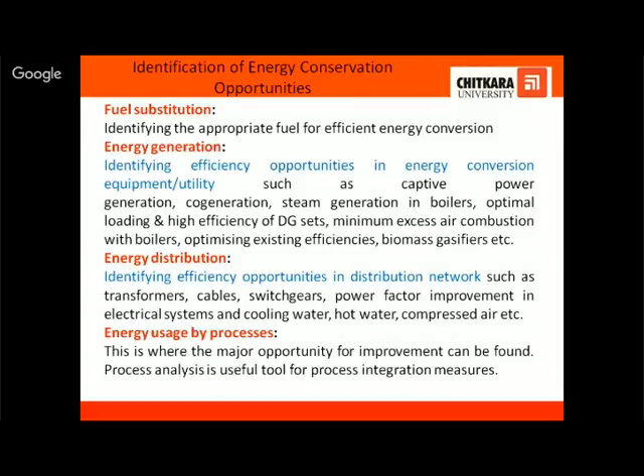Then we talk about the energy distribution systems. We can work out where energy efficient opportunities exist, like in transformers and cables. If there are loose joints of the cables, or the terminations are not done properly, then a lot of energy gets wasted. And sometimes the cables are overloaded. If they are not sized properly, then again power loss is occurring. Then what about the switchgear? If the power factor needs to be improved, then compressed air systems, cooling water. So the complete energy distribution system.